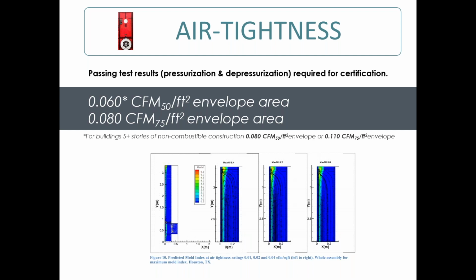So just for comparison, the 0.06 CFM50 per square foot for maybe a 2,500 square foot residential single family home is roughly 1 ACH50. It goes lower for larger buildings and higher for smaller buildings, or rather for buildings with more envelope area relative to floor area. And then you can test it at 75 pascals, and there's a higher limit there.